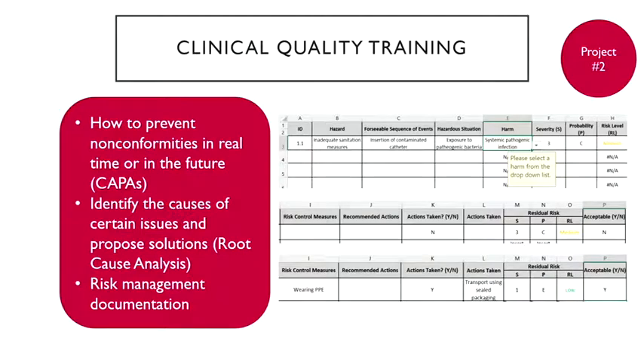So if we take actions like wearing personal protective equipment or transporting our catheter using sealed packaging, now our residual risk level has dropped to a severity level of 1, a probability of class E, which now outputs a low risk level.